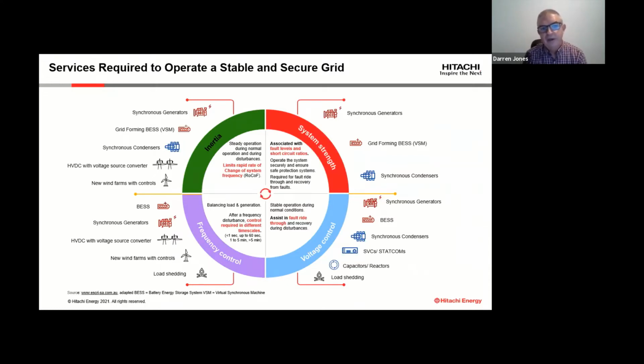The main thing to bring out here, on the right-hand side, is system strength and voltage control. Electricity network owners and operators have a statutory legal duty to keep voltage within certain limits, to make sure equipment connected to the network can function correctly. If voltage is too high it could cause damage to customers' connected equipment, and the converse is true - if voltage is too low, that can also cause maloperation.